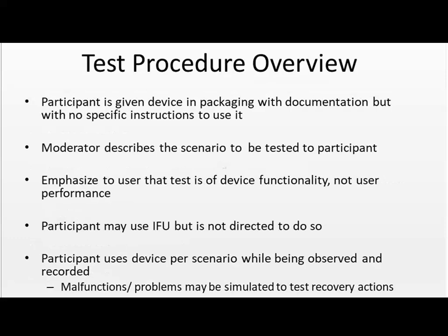An overview of the actual test procedure. The participant is given the device in its packaging with its documentation, but with no specific instructions to use the documentations. The moderator describes the scenario to be tested to the participant. It's important to emphasize to the user that the test is of device functionality, not user performance.